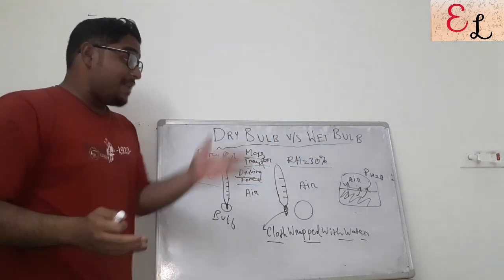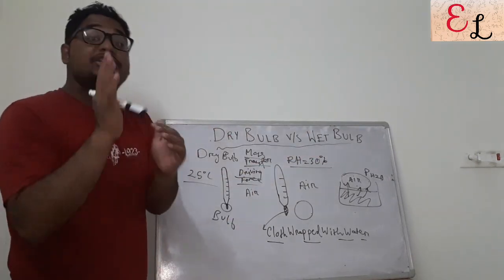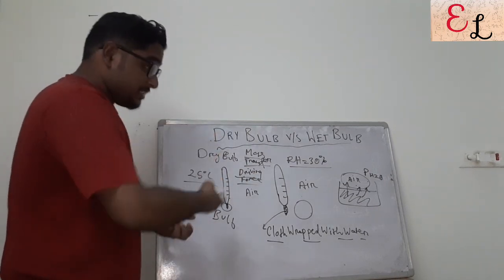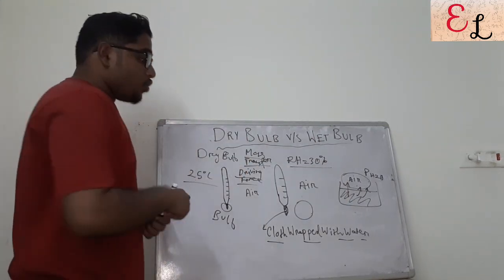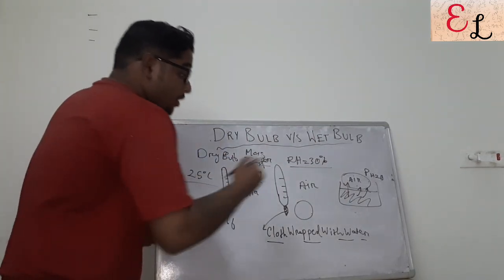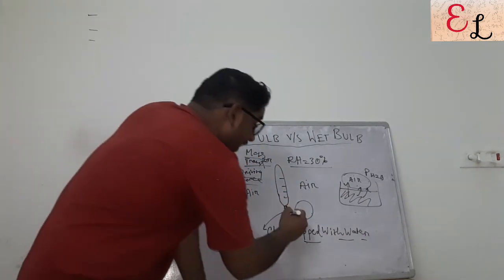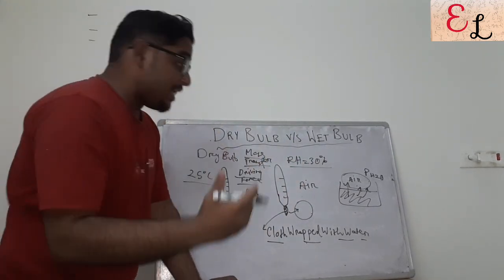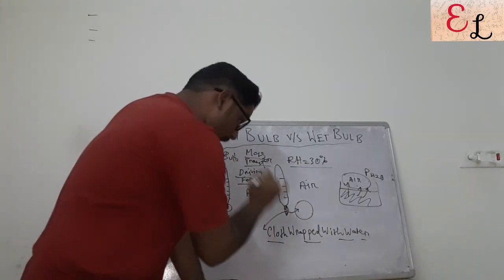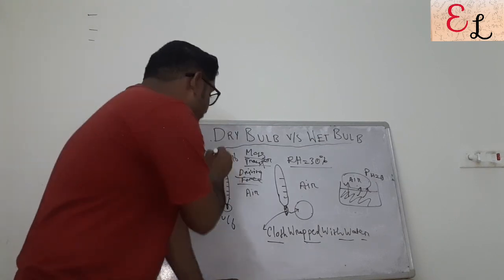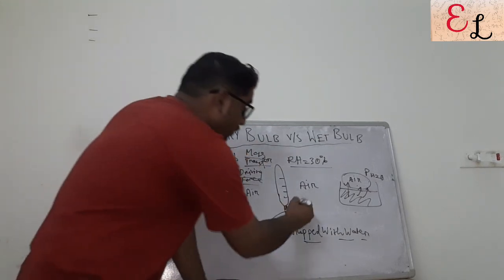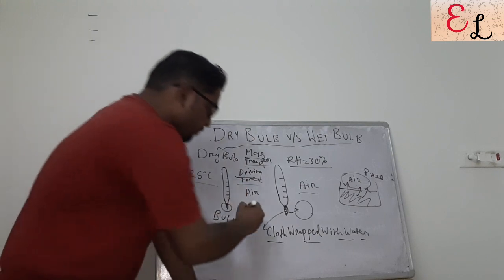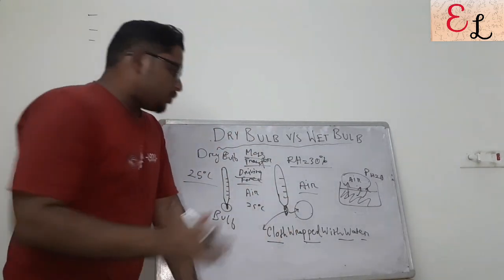Because of this mass transfer driving force, due to the difference in partial pressure, water tends to evaporate as water vapor into the air, trying to saturate it — that is, the relative humidity of air increases. So whenever we wrap this bulb with a wet cloth, the water will try to evaporate into the atmosphere. If the relative humidity is 100%, then dry bulb temperature equals wet bulb temperature, because there will simply be a sensible heat transfer from air to the bulb.